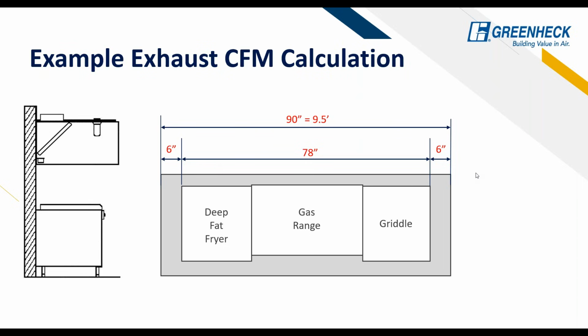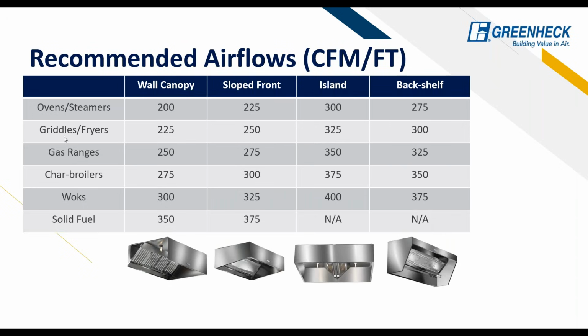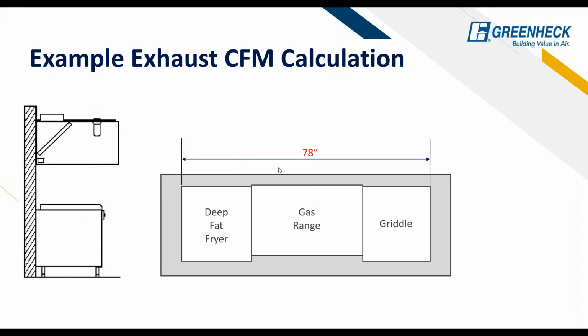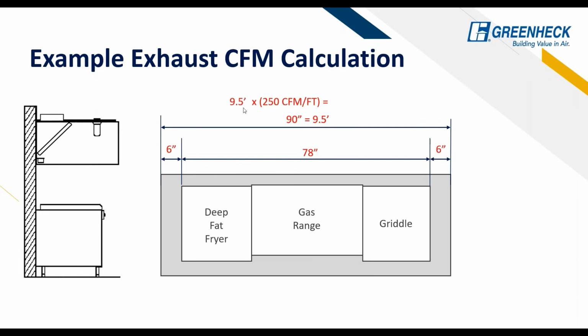Now we look at these appliances: we have a fryer, we have a range, and we have a griddle. If we go back to this page, we have a range, a fryer, and a griddle, and we're looking at 225 CFM or 250 CFM. Because the gas range requires 250 CFM, we have to go with the most, so we have to go with the highest value there. With the gas range, 9.5 feet, we'll use 250 CFM per foot, and we have an exhaust rate of 2,375 CFM.